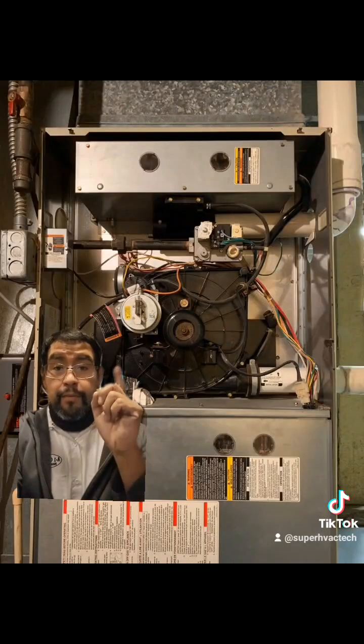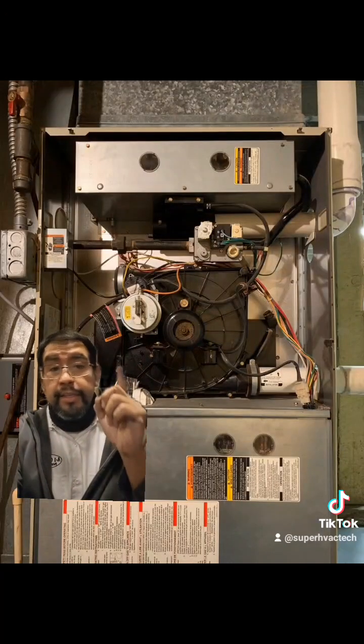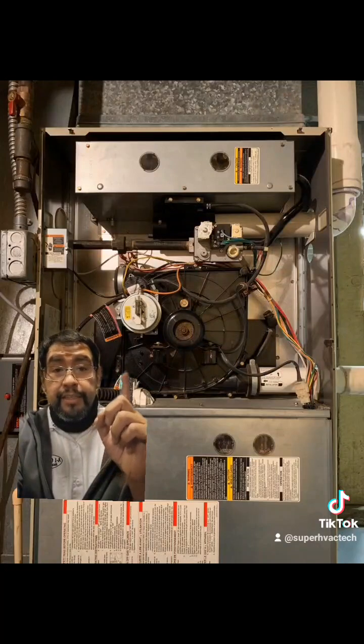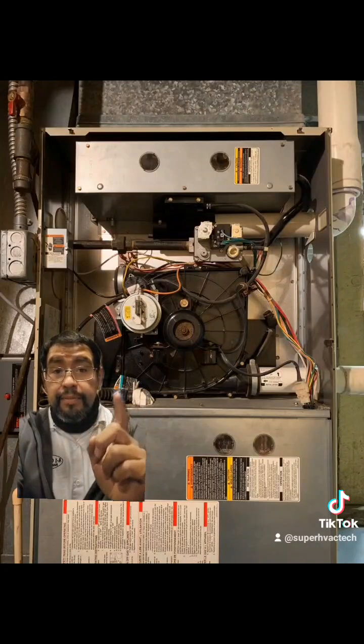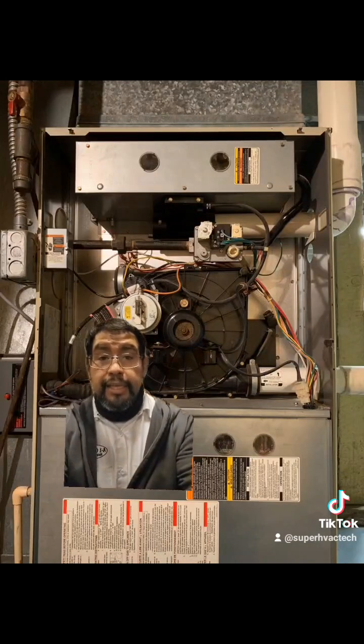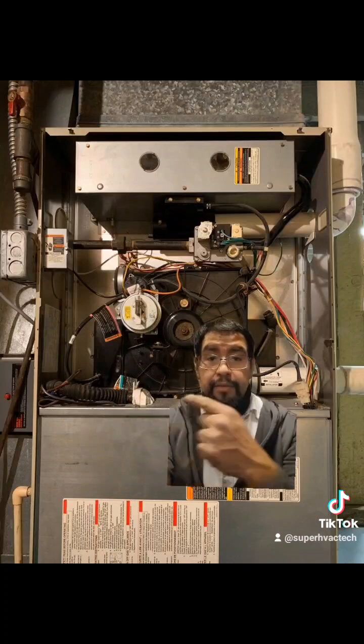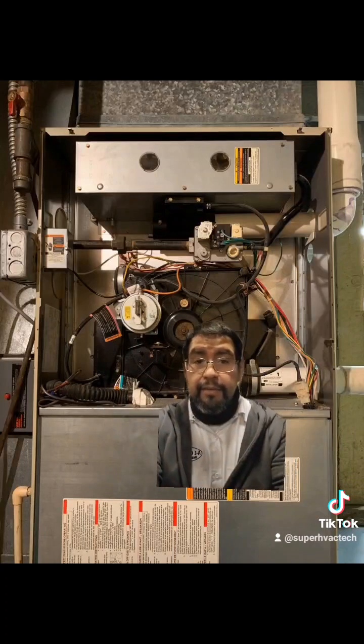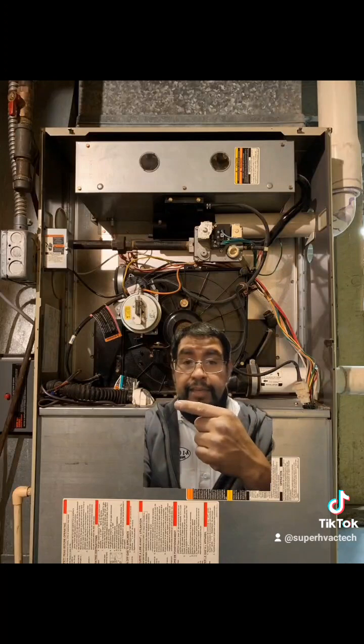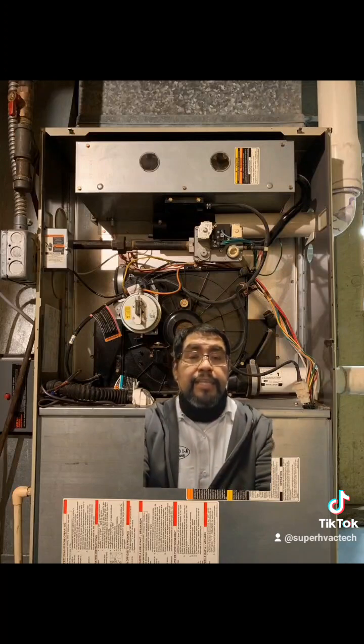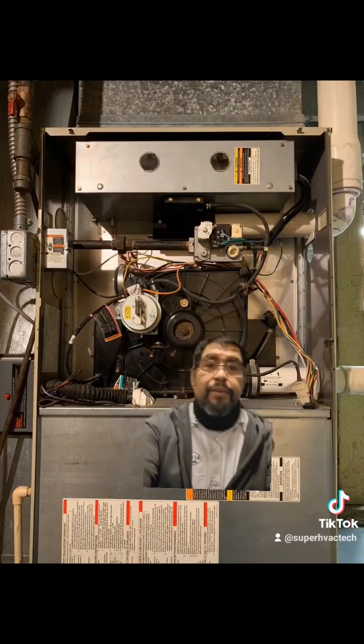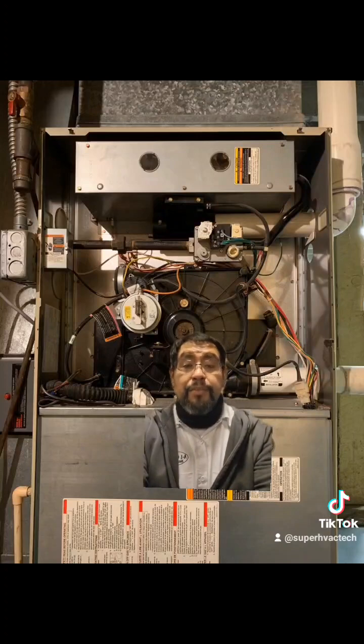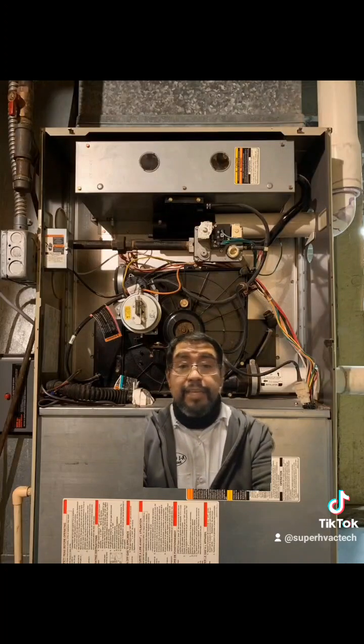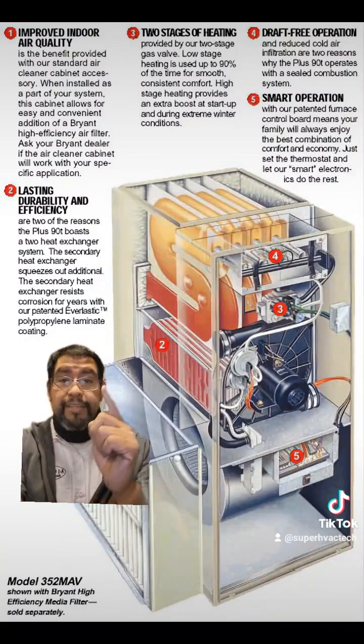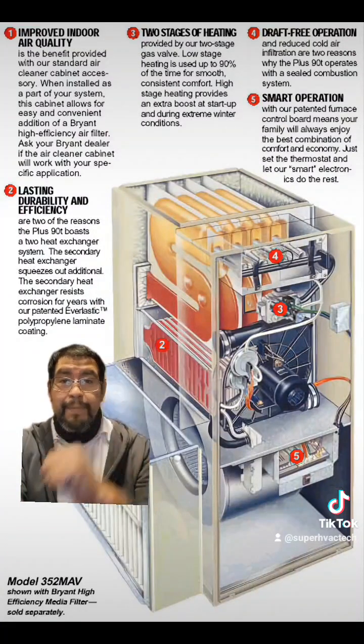Also, speaking of, and this is only for Weathermakers, 90% efficient furnaces, they have an issue with the heat exchangers. Right there, if you look at your drain lines, these heat exchangers, back when they got built, Carrier thought that in order to preserve the integrity of the heat exchanger - just pause and read that right there.